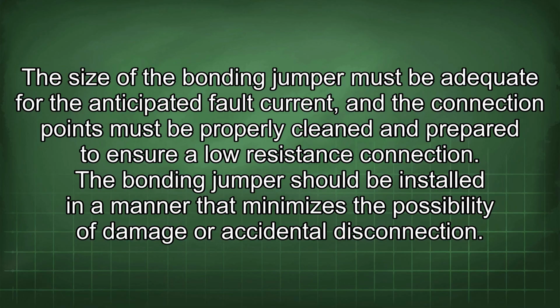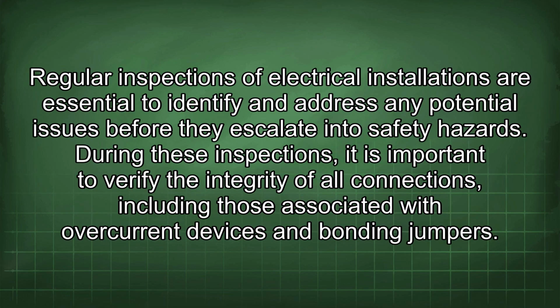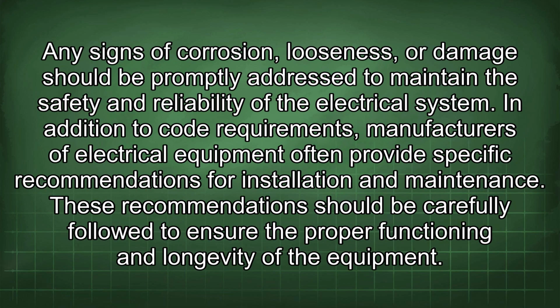The bonding jumper should be installed in a manner that minimizes the possibility of damage or accidental disconnection. Regular inspections of electrical installations are essential to identify and address any potential issues before they escalate into safety hazards. During these inspections, it is important to verify the integrity of all connections, including those associated with overcurrent devices and bonding jumpers.